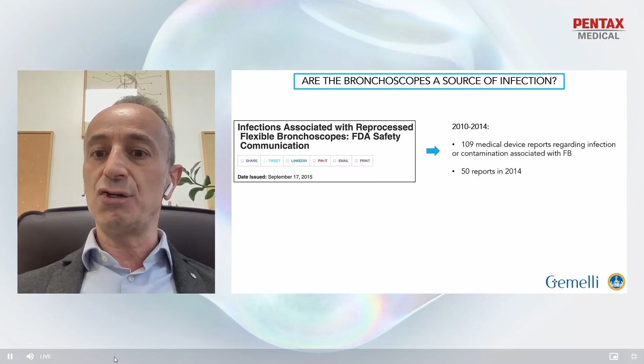In 2015, the FDA came up with a safety communication after receiving more than 100 medical device reports regarding infections or contaminated bronchoscopes transmitting infections. And most of these reports came out in the last year of their analysis, which was 2014. In 2021, there was a new safety communication issued by the FDA.